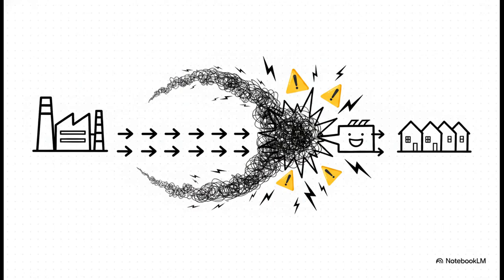When you improperly place a distributed generator, you're suddenly pumping a massive traffic jam of local electrons onto a small grid road that wasn't built for it. If the local generator produces more power than the neighborhood is using at that moment, the excess power forces its way backwards up the grid, causing reverse power flow. Like water pressure building up in a blocked pipe, this reverse flow causes dangerous voltage spikes, or voltage rise, which can fry equipment and trigger protective relays to shut the whole system down.